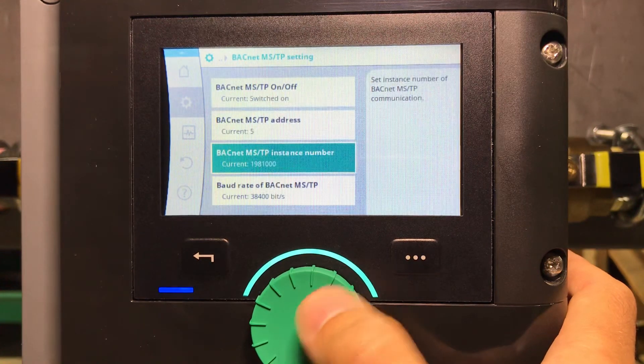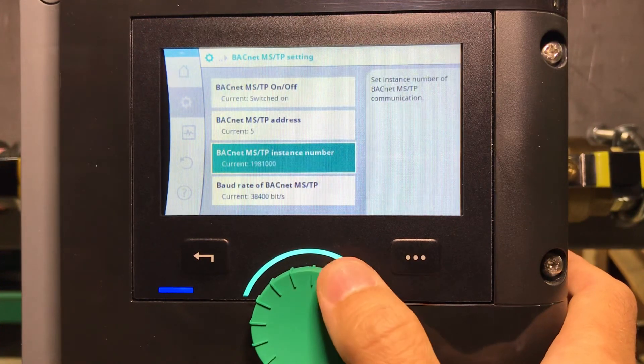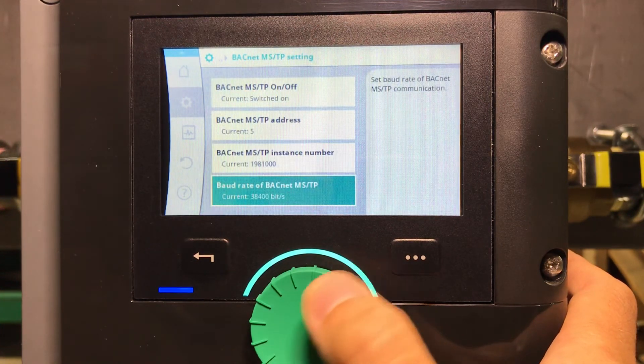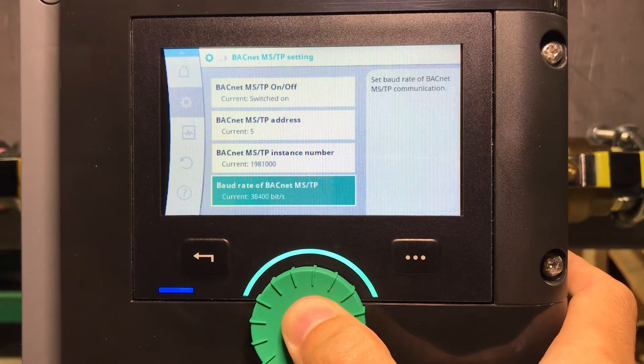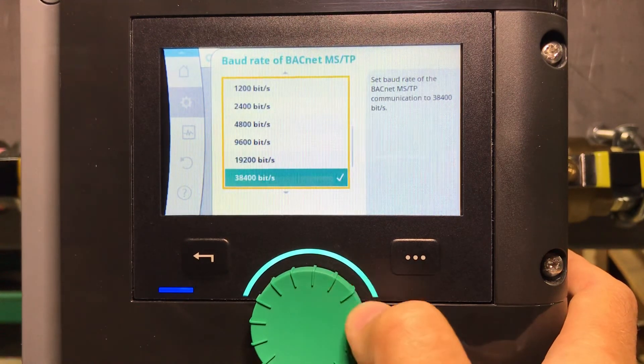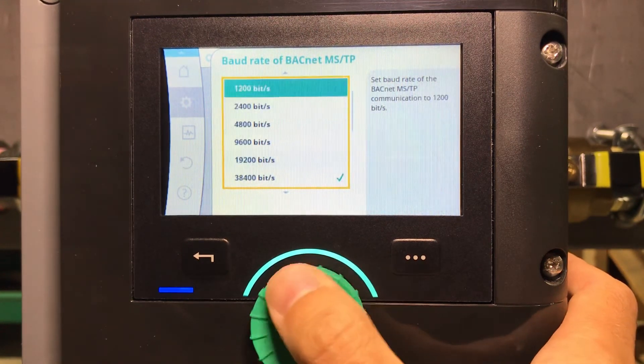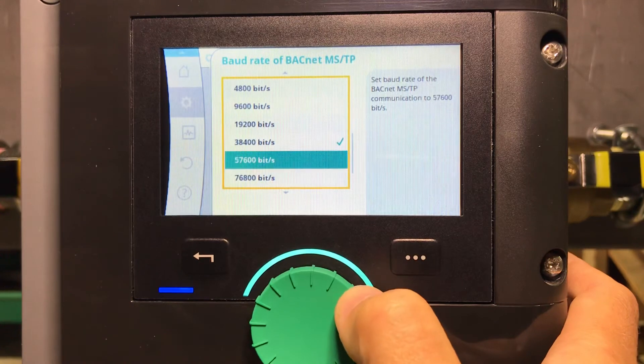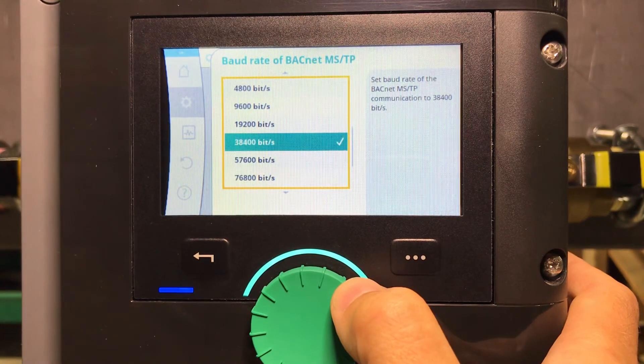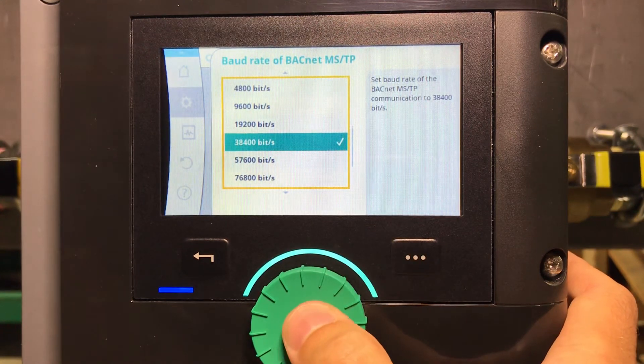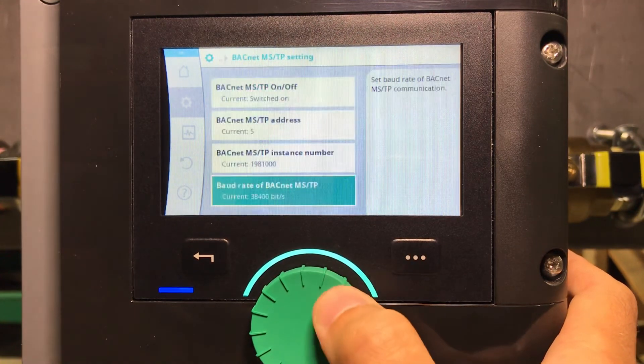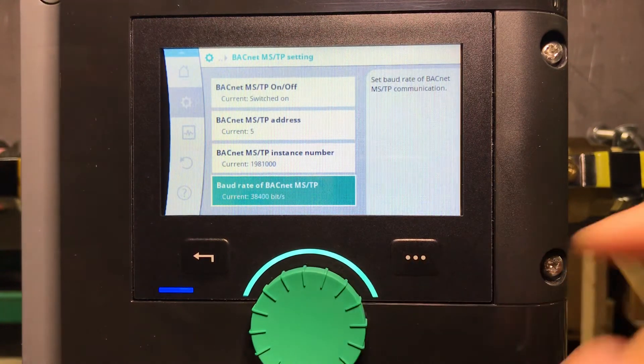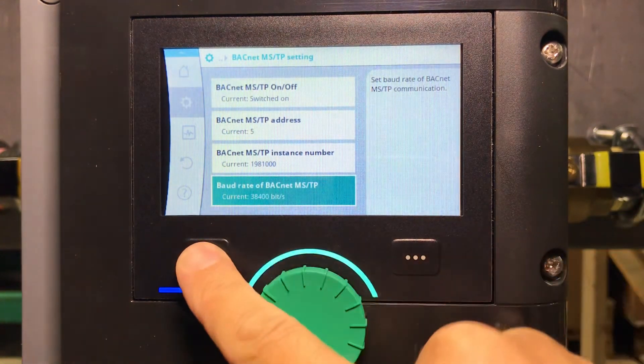That's it — you've set up your instance number. Of course, you also want to select the baud rate, which is the speed of your network. The default is 38,400 — let's leave it at that. Right now the pump is communicating through BACnet.